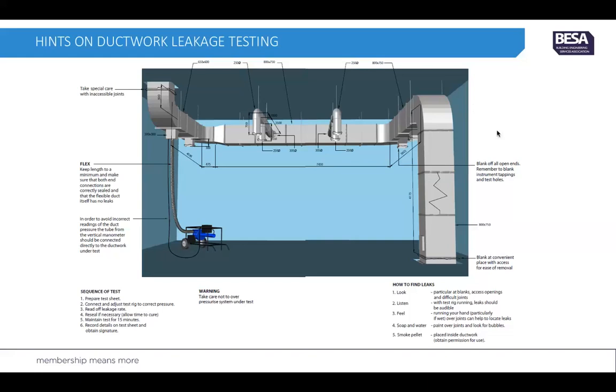The sequence of the tests would be: prepare the test sheet; connect and adjust the test rig to the correct pressure that the specification calls for; read off the leakage rates; reseal the ductwork if necessary and allow time for the sealant to cure — normally about 15 minutes; retest until you achieve the correct pressure; then record the details onto the test sheet and obtain the signature from the witness.